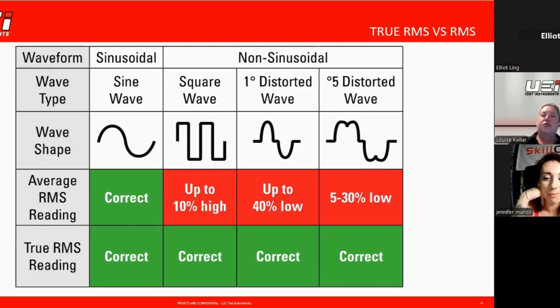But what true RMS does is basically, as it's taking its reading, it slows down a little bit in the meter so it can analyze it. So now when you start seeing those peaks and valleys, or that one-off thing that might happen every so often, you're going to be able to see that. True RMS is going to give you a more accurate read.